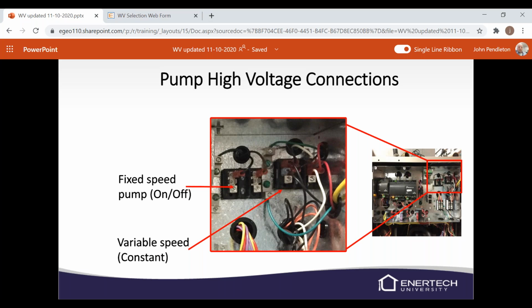I really wish that the blower motors, when you unplug the low voltage, would go to 100% as well, because that's what usually fails on a blower, is the module. So it'd be nice if they would do the same thing these pumps did, get confused and just go to 100%. I mean, it's better to have some flow than no flow. But I guess that's not real relevant to this training, but sometimes things get on my mind and I say something.